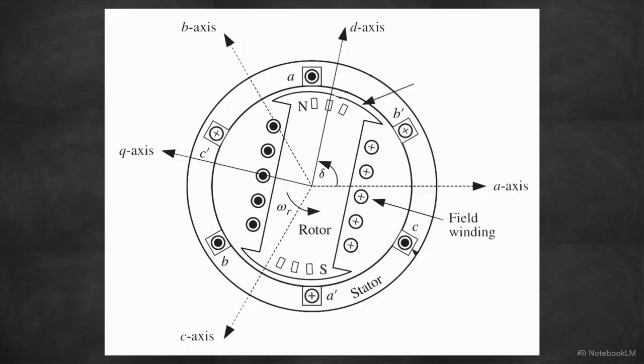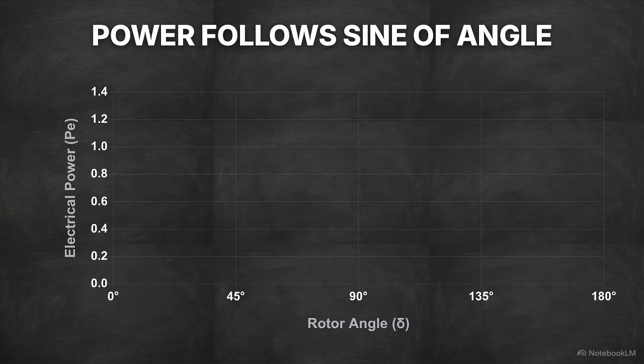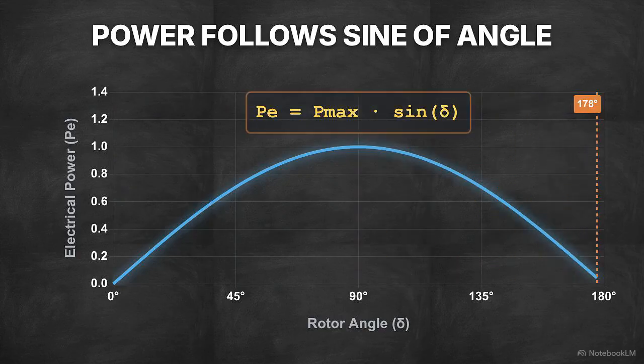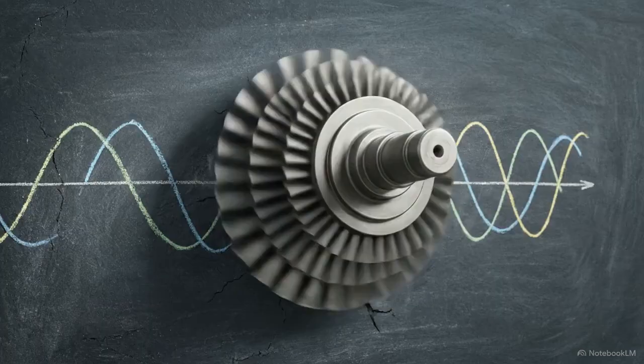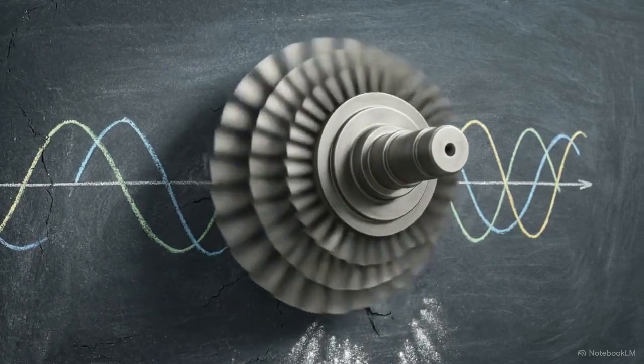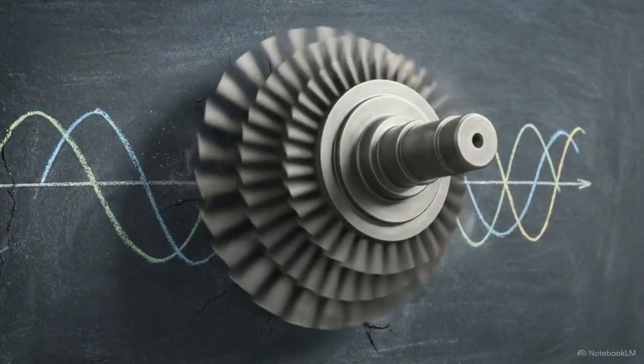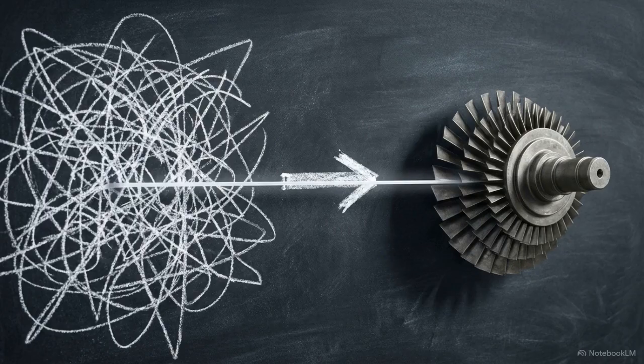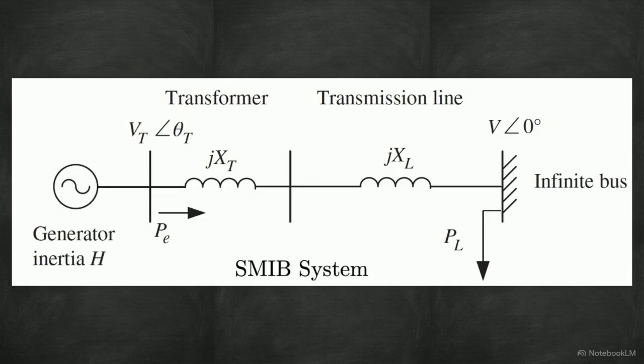This is the literal electrical angle between the internal rotor's magnetic axis and the rotating reference field of the grid. The swing equation is nonlinear because electrical power is tied to the sine of this angle. Because of this sine-delta nonlinearity, engineers cannot use standard linear tools to predict survival. They must mathematically track the physical swing of the rotor to see if it remains within stable limits. To solve for a single machine's survival, engineers simplified the chaotic complexity of the national grid. They used the single machine infinite bus model, or SMIB. The infinite bus acts as a perfect, unyielding voltage reference. It represents the collective strength of the rest of the grid, which cannot be shifted by our single generator.